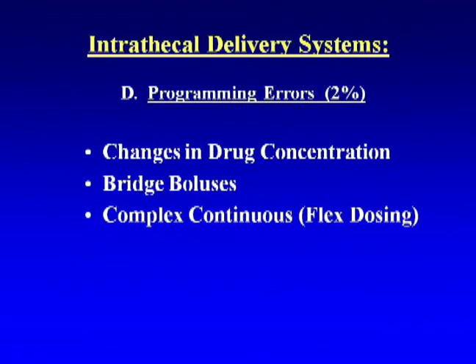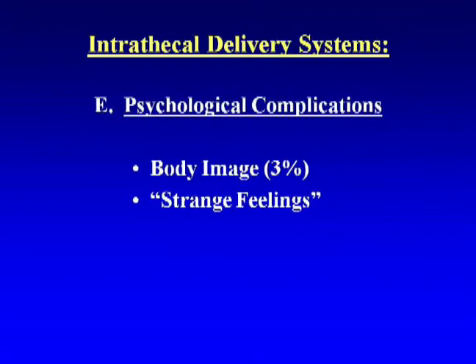Programming errors account for about 2% of the total 44% complication rate. They occur when making changes in drug concentration requiring reprogramming, and if you make a mistake going off by one decimal point, that's a factor of 10. Bridge bolus and flex dosing — formerly called complex continuous in the SynchroMed II pump — are also potential sources for programming error.